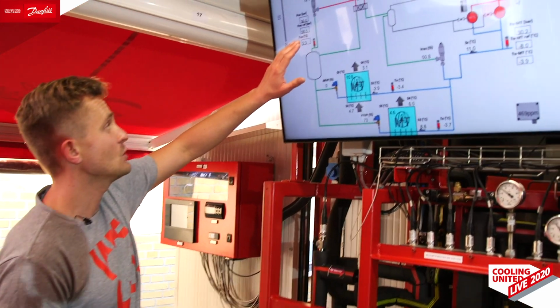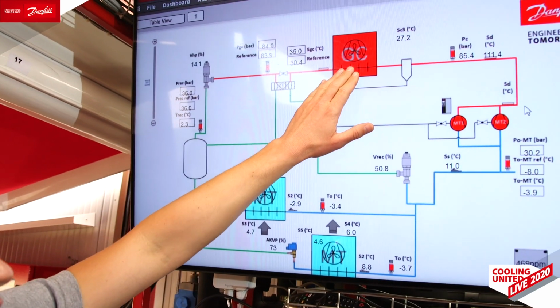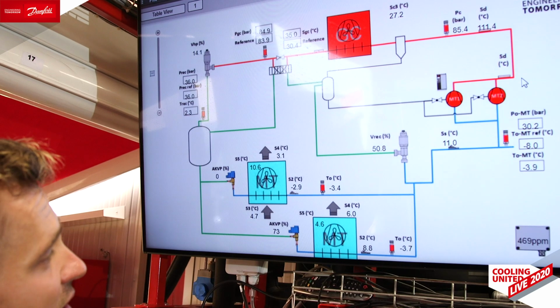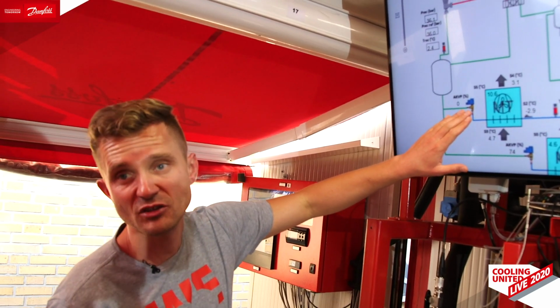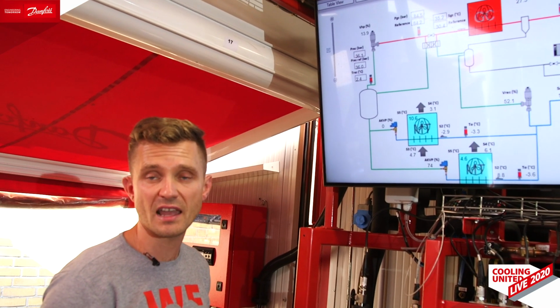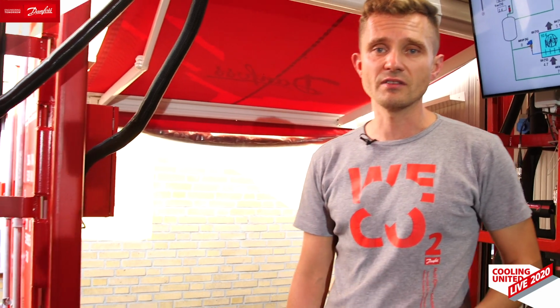Firstly, they can be used as the high pressure valve, taking care of the pressure inside of the gas cooler. You will also find them between the receiver and the compressors, acting as the gas bypass valve. And finally, they can also be used as expansion valves for evaporators. In this case, we have the AKVP, but they can be easily replaced by the CCMT valves. Follow me and let's have a look at the family of the CCMT valves.